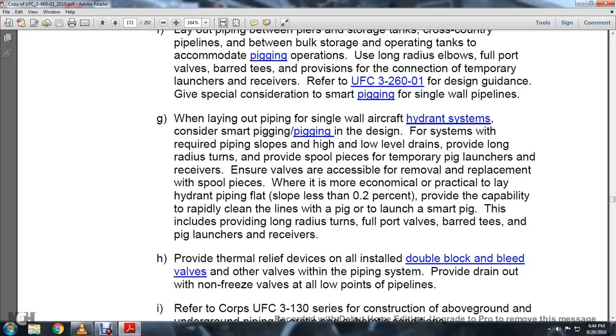Where it is economically practical, lay the hydrant piping flat with a slope less than 0.2%, provide the capability to rapidly clean the lines with a pig or to launch a smart pig. This includes providing long radius turns, full port valves, barred tees, and pig launchers and receivers.